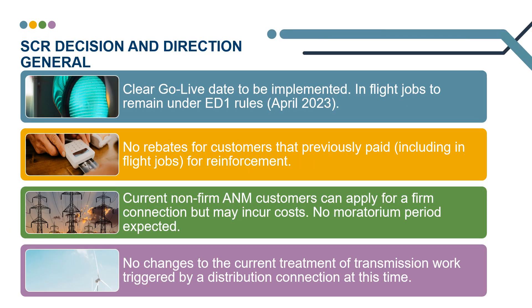Points to make clear: there will be a clear go live date to be implemented, which is April 2023. In-flight jobs will remain under ED1 rules. There will be no rebates for customers that have previously paid, including in-flight jobs, for reinforcement. Current non-firm ANM customers can apply for a firm connection but may incur costs. No moratorium period is expected. There are no changes to the current treatment of transmission work triggered by a distribution connection at this time. If there is a transmission constraint that may be five or six years before it is lifted, you can still request a flexible connection; however, there will be no guaranteed curtailment limit and/or end date because it is subject to a transmission constraint.